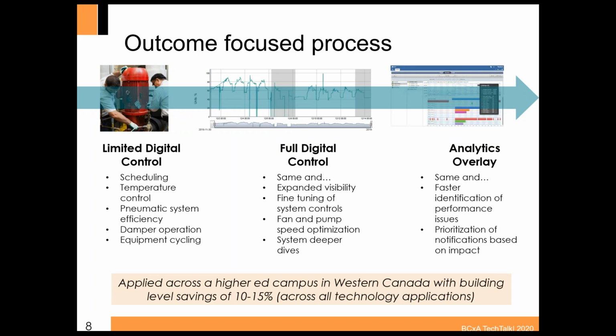From the pneumatic systems, we're working with the client on focusing on what I think many would call the low-hanging fruit, but it has a really big impact. So scheduling, temperature control, the pneumatic system efficiency itself. There's a lot of losses with pneumatics in general. The damper operations, which I'll actually talk a little bit more about with an example. Equipment cycling on and off. There's quite a bit that you can manage from a process standpoint and evaluate even with a pneumatic system, though you're having to go into the field to validate or use data loggers to get that information needed.